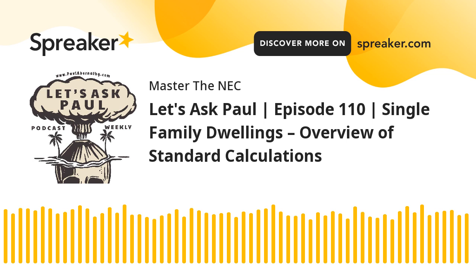And that's the value that we would put. And that would be our next step. Just remember, if you don't have 4, if you have 3 or less, then you're just not going to apply any multiplier of 75%. You just take it at whatever the value is and you're just going to add them all up. And that's your contribution for that step.